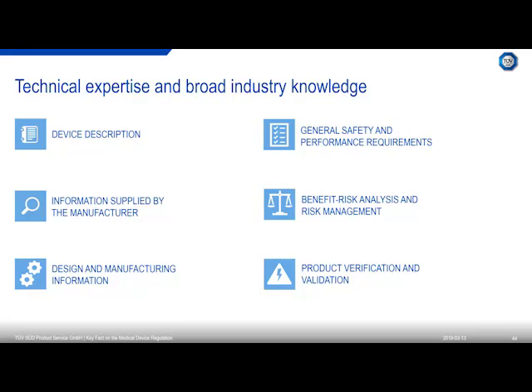So if we have now the device description covered, then we talk about the information supplied by the manufacturer, which is typically labels and instructions for use. And what the MDR requires here is a complete set of labels on the device and packaging in the language accepted in the member states where the device is envisaged to be sold.